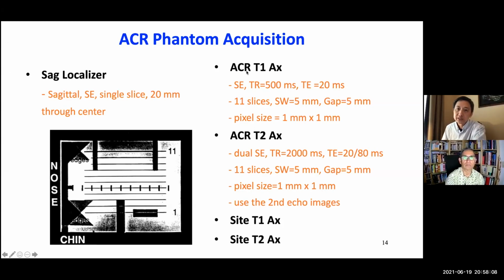The first scan is the ACR axial T1 scan. That's a spin echo sequence with TR 500, TE 20 milliseconds. 11 slices, 5 millimeter slice thickness and 5 millimeter gap. And the pixel size should be 1 millimeter by 1 millimeter. So typically we set field of view 256 with 256 matrix. So the pixel size will be 1 millimeter.